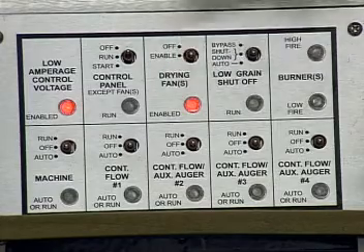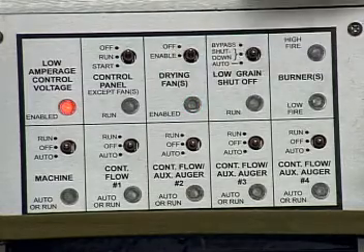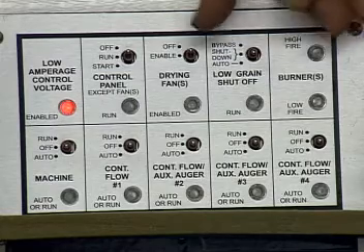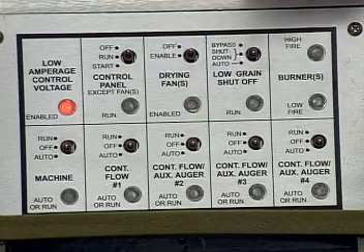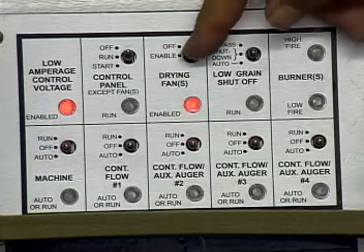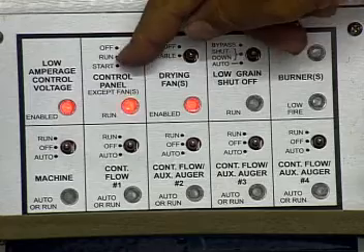You physically can go out and start the fan now. With that in the off position, you can't do it. So the reverse is true also. If the fans were running right now and you needed to shut the fans off, you can turn that and shut the fans off because it breaks the safety circuit. So we're going to turn that on. We're going to go back and start this up.